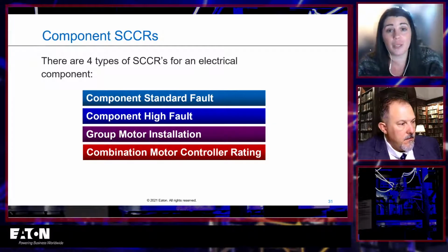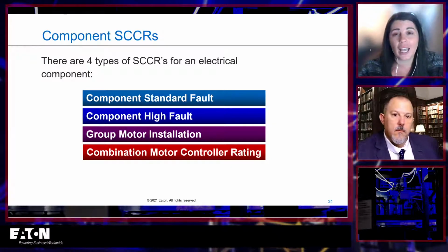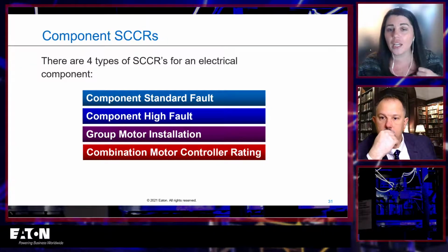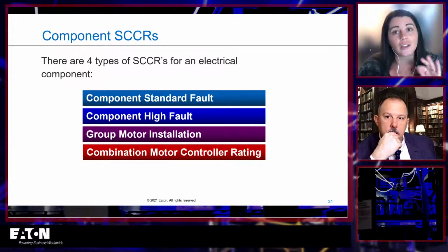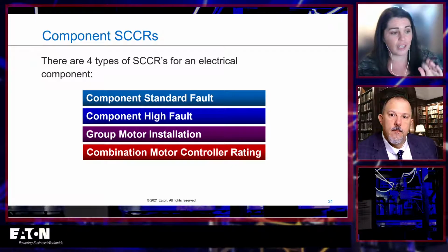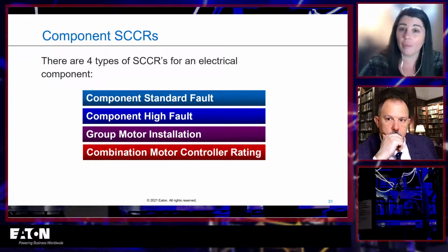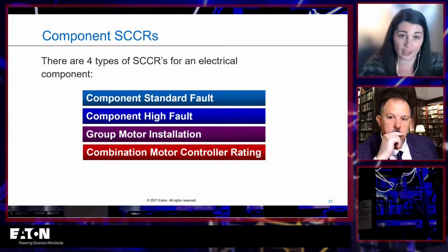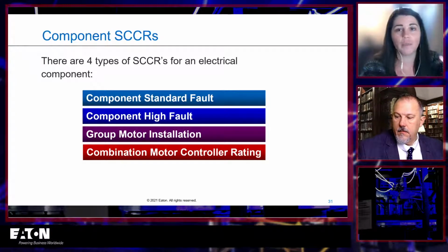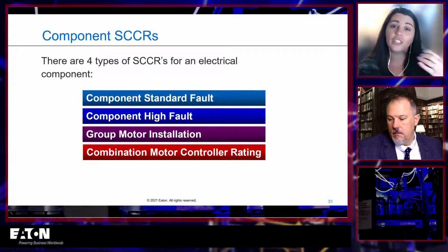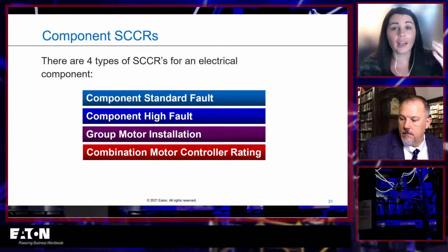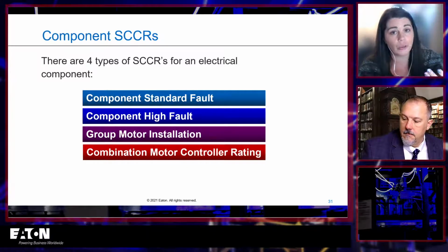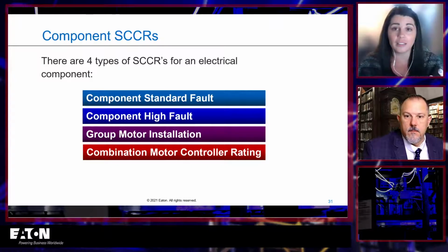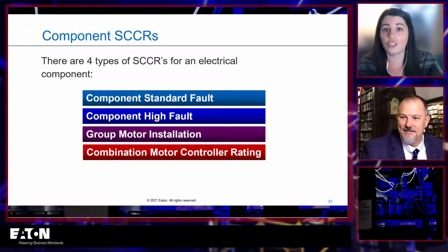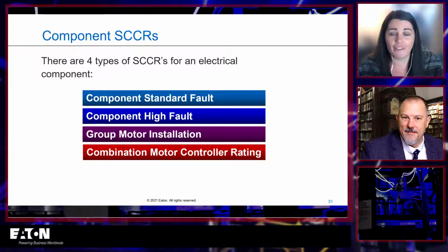So the next type is going to be a high fault rating. A high fault rating is kind of like a generic combination rating, in that it's not necessarily part number specific, right? This might be a rating where it says, if you have a contactor and that contactor is normally 5 kA, but if you put a 30 amp class J fuse in front of it, now it's 100 kA. It didn't call out specifically Bussmann LPJ-30SP, right? It just said any 30 amp class J fuse. That makes it sort of the high fault rating, that generic optional higher rating. It's actually been tested and listed with UL that these two things together will achieve this higher rating. So that's your high fault rating.